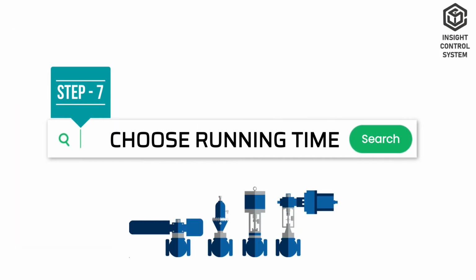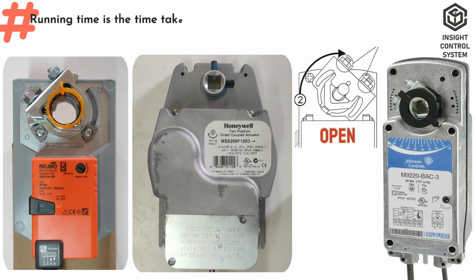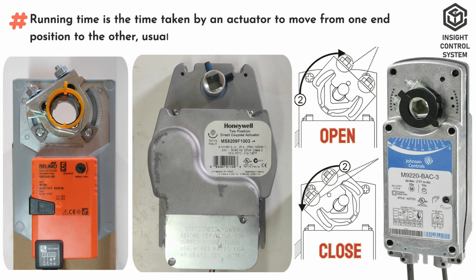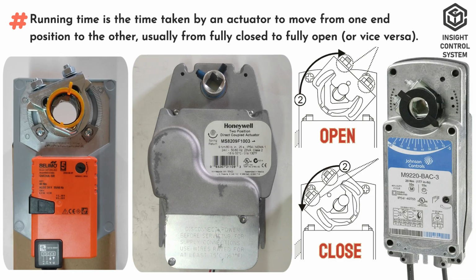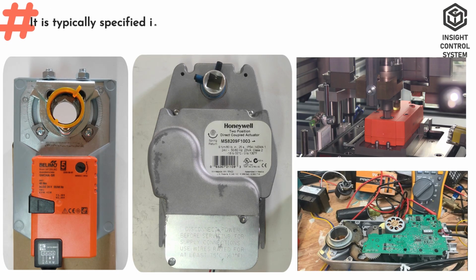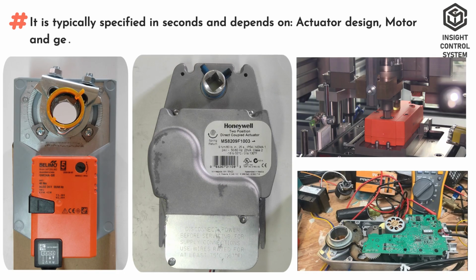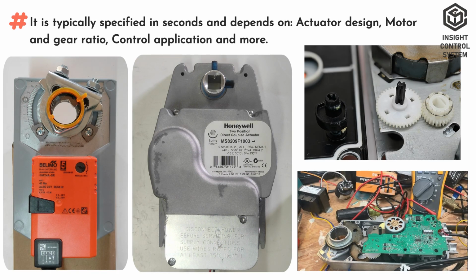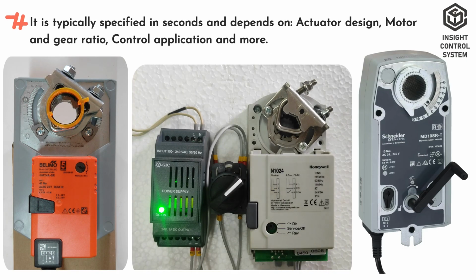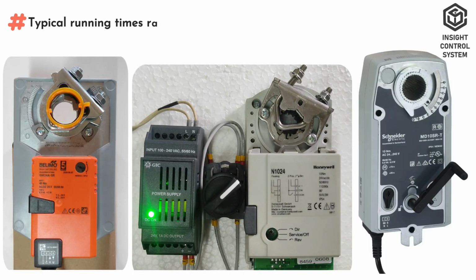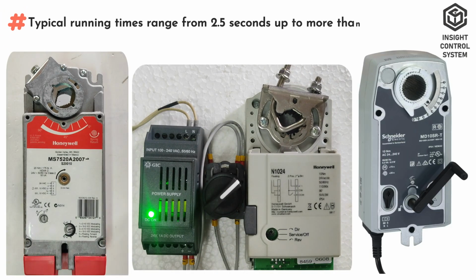Step 7. Choose the running time. Running time is the time taken by an actuator to move from one end position to the other, usually from fully closed to fully open, or vice versa. It is typically specified in seconds and depends on actuator design, motor and gear ratio, control application, and more. Typical running times range from 2.5 seconds up to more than 150 seconds.